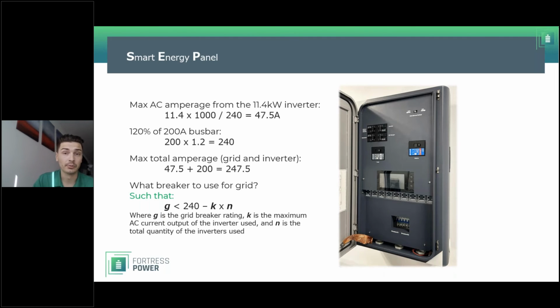One thing to note: how long can we back up that 200 amp pass-through? You don't want to say you can do 200 amps for 10 hours, that's not what I'm saying. What I'm saying is you can have very heavy loads on the smart energy panel. You can shed the heavy loads and provide 200 amps of backup, and more, to the most important loads, or the loads your customer deems most important, all done through the programming app.